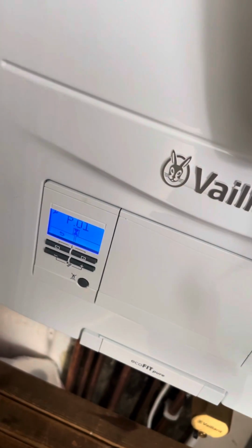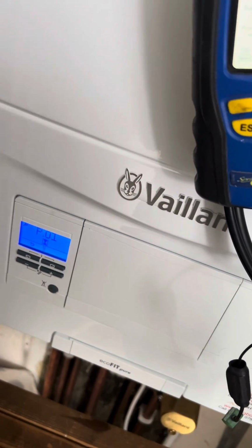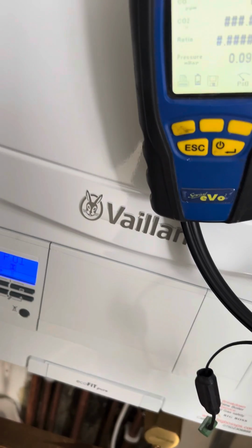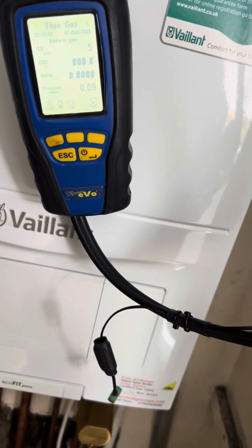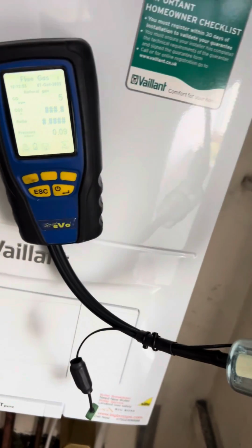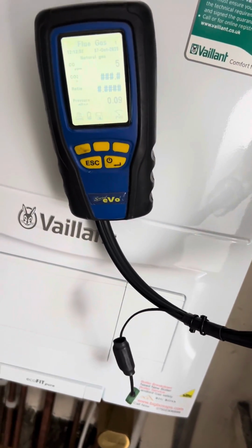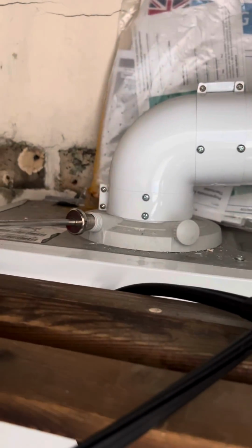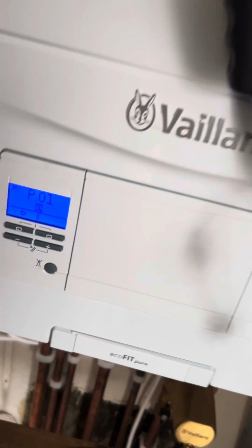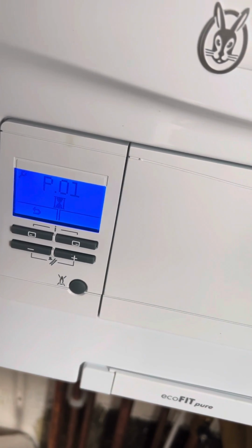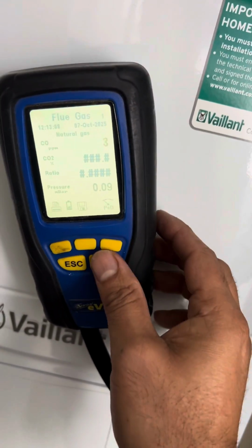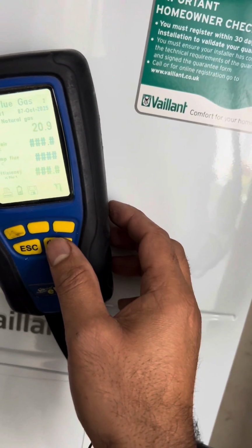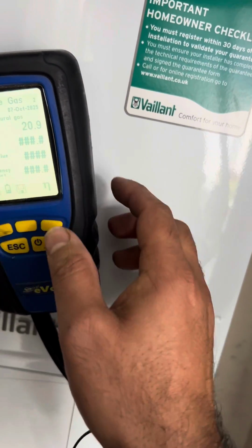So our third very important check is the flue integrity test. We have to do this every time when we test the boiler, to check the flue is in good condition and there are no gases mixing with the oxygen. On the Vaillant it is on the right side. You need to put your probe in, and then in the program you need to do P01 as I explained in the procedure first, and in the end we need to press this power button. So now we can see the O2.